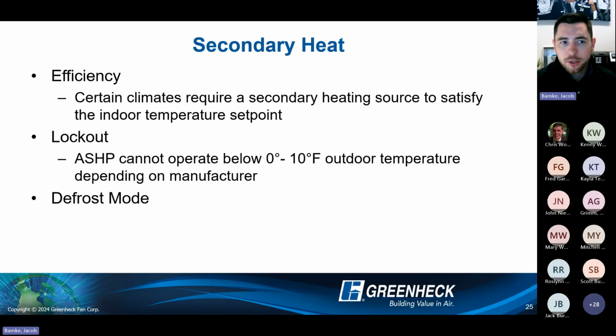And that's that first bullet point you see. Efficiency, if it drops enough, certain climates, those colder climates, are going to require a secondary heat source to make sure you can satisfy that discharge temperature set point requirement. The other things that you have to look at is, are you in an area where your heat pump is going to lock out? So typically an air source heat pump cannot operate below 0 to 10 degrees outdoor temperature, depending on manufacturer. Another thing you'll have to look at is there's certain indoor coil entering air temperature requirements as well. So it's not just ambient. Sometimes it's in conjunction with some minimums entering the indoor coil. But that could be another reason why you would need a secondary heat source.